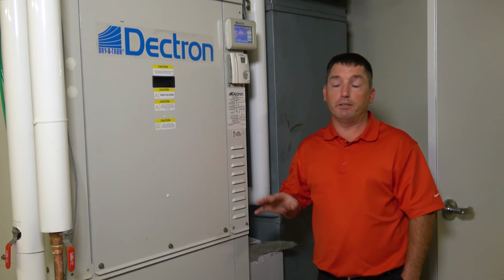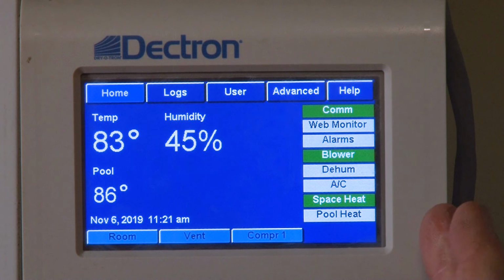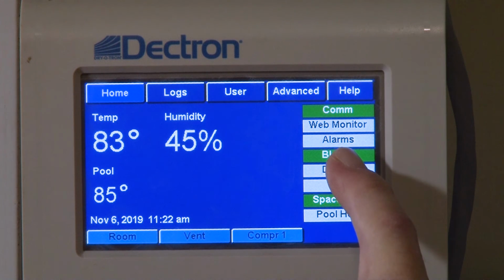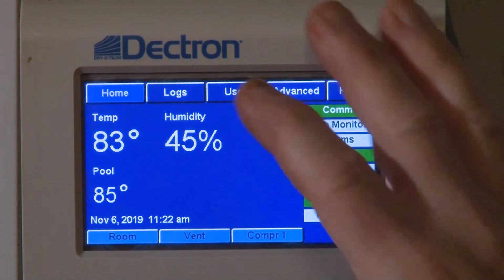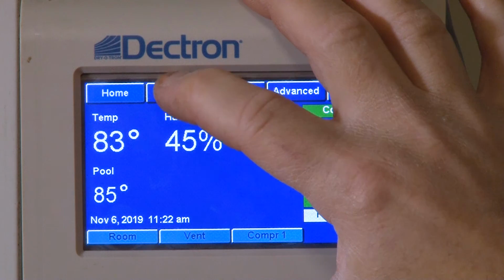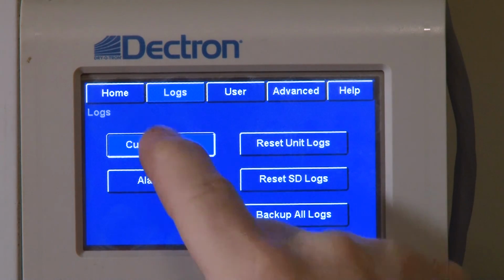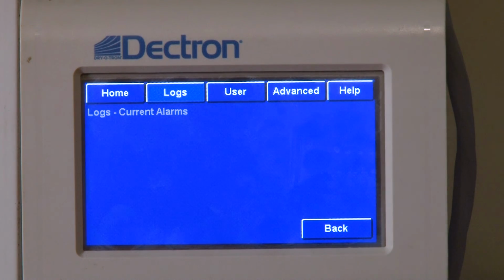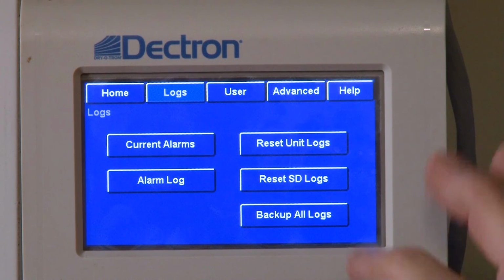During normal operation, everything is going to be green. Green is good, obviously. If we have an issue and a sensor goes out of range or something happens that the unit doesn't start properly, the alarm indicator is going to light up in red to indicate that there's an alarm. To check that, you want to go into logs and the current alarms. Right now we don't have any alarms present, so none are showing.